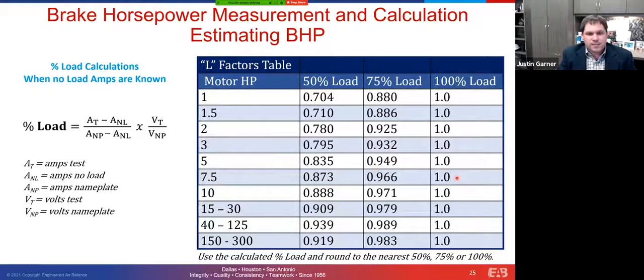And then we have this L factors table. This is an L factors table that's published in the AABC technician training manual. It might also be in the national standards. It's a condensed version. There are some that are out there that are very, very detailed and break down almost every single percentage. And so you don't have to go through here and interpolate and things like that. But for the purposes of this calculation, we're going to use this table. And we're just going to estimate and go to the nearest L factor that's shown here and not try to do any crazy interpolation, because it really doesn't make that big of a difference in the end. One thing to note, though, as I was talking about earlier, this L factor doesn't matter at 100% load. So if we're fully loaded, you can see it's one, it's negligible.